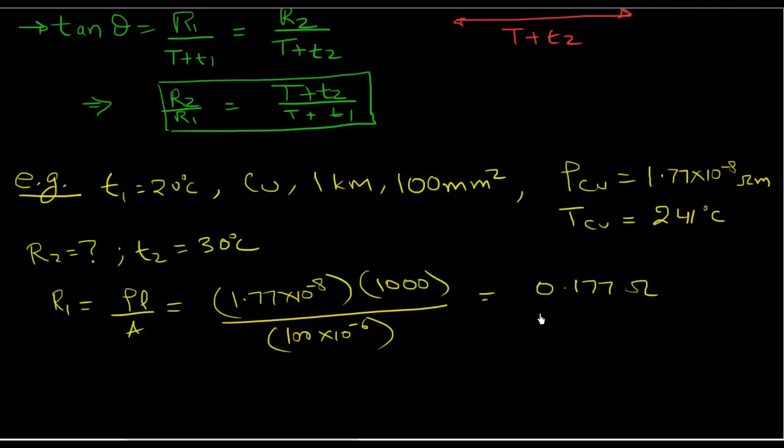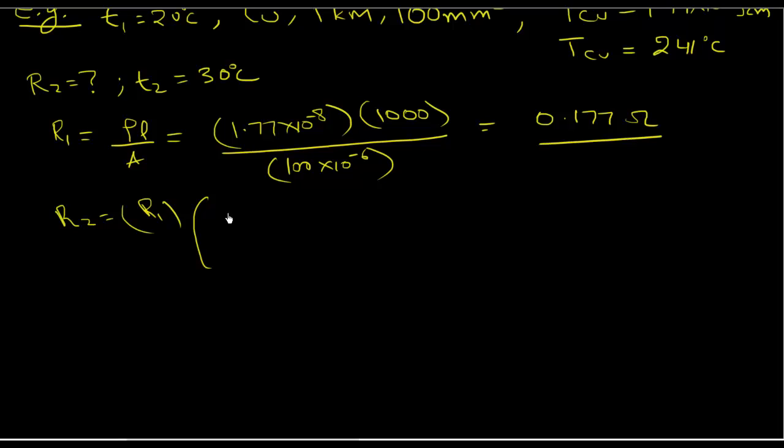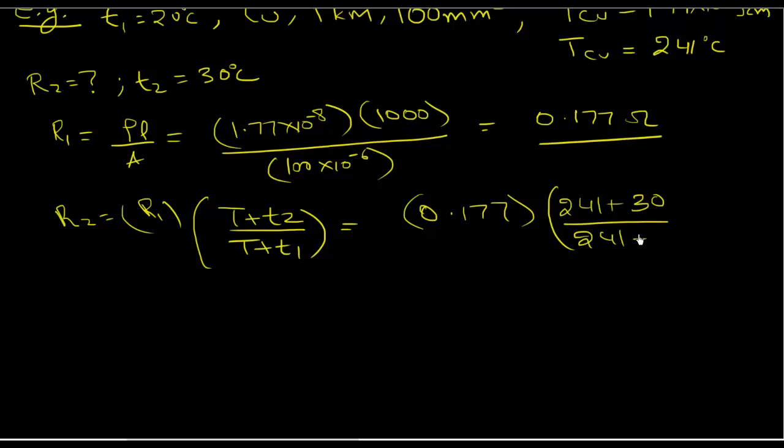So that's my R1. My R2 then is simply going to be R1 times, let me write this a little bit properly. R1 times T plus T2 over T plus T1. So that will be 0.177 times 241 plus 30 over 241 plus 20. And I believe if you put those values in your calculator, you're going to get a value of 0.1837 ohms.